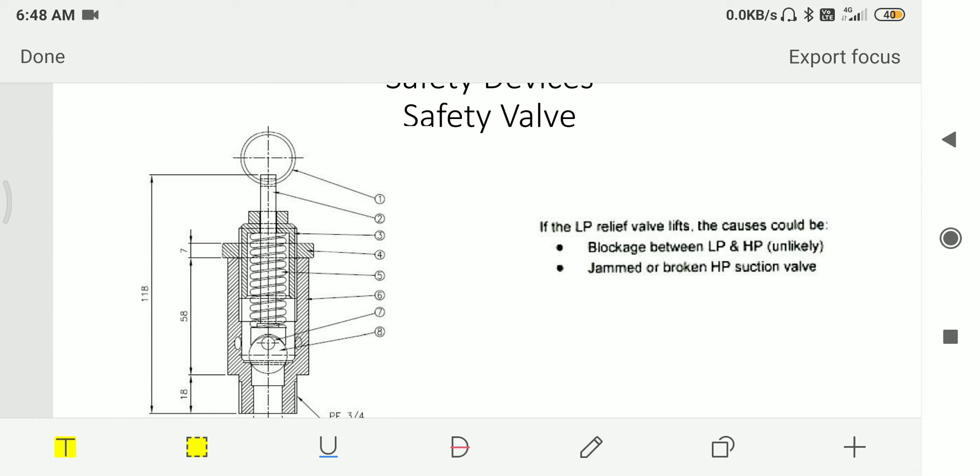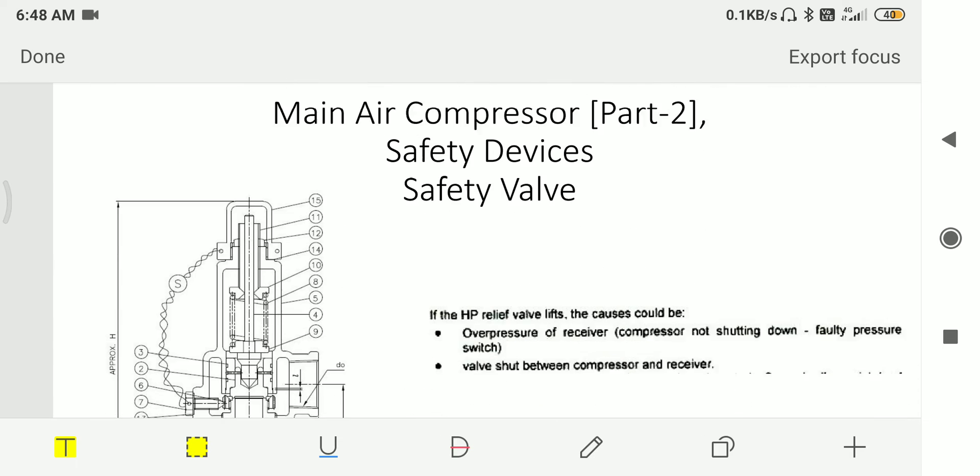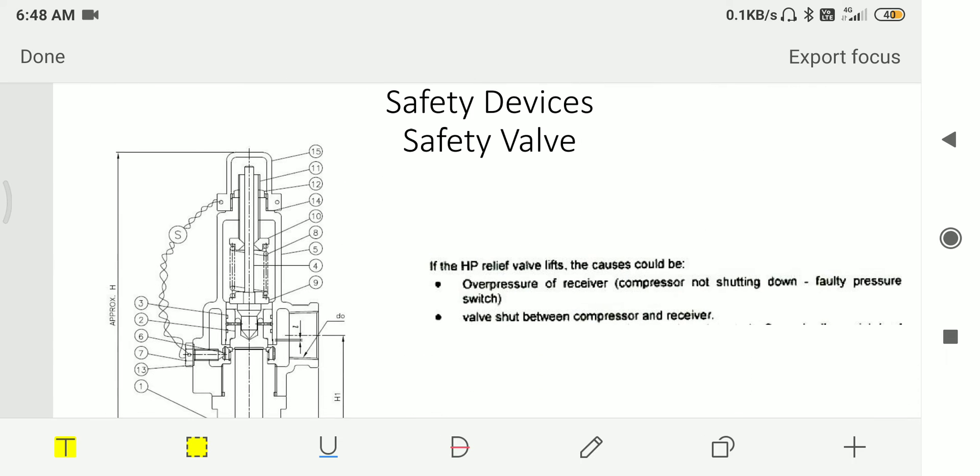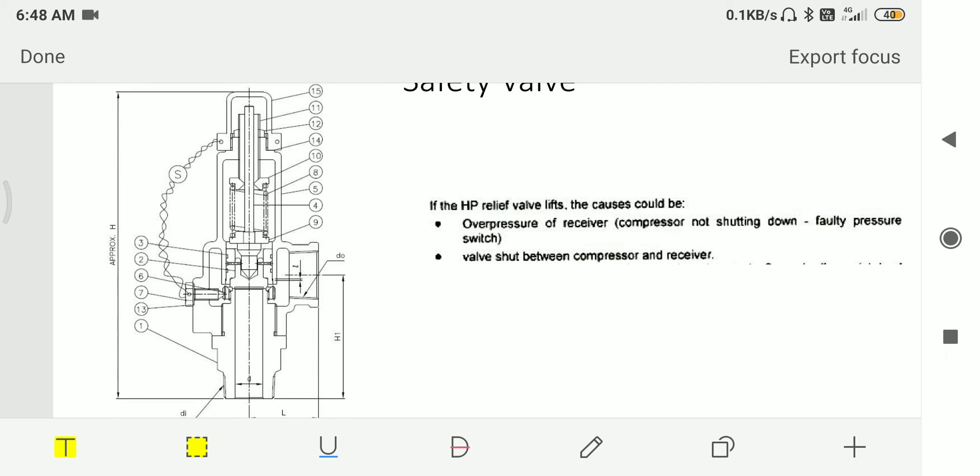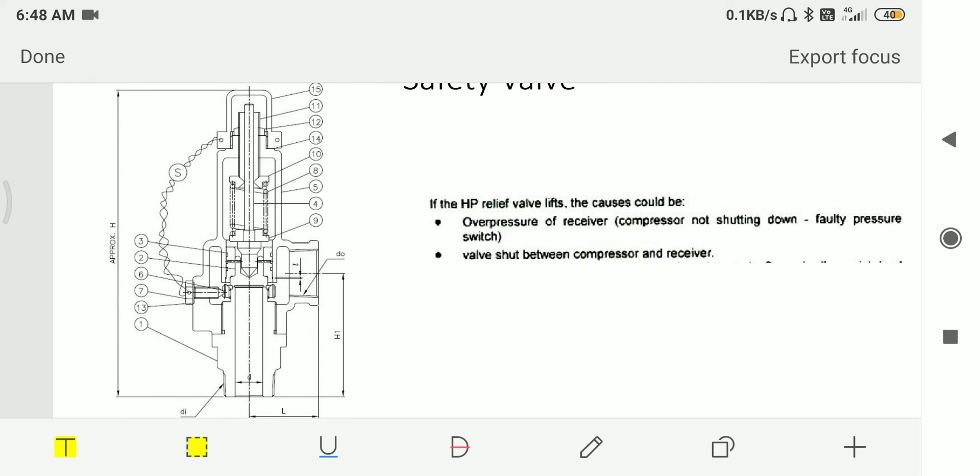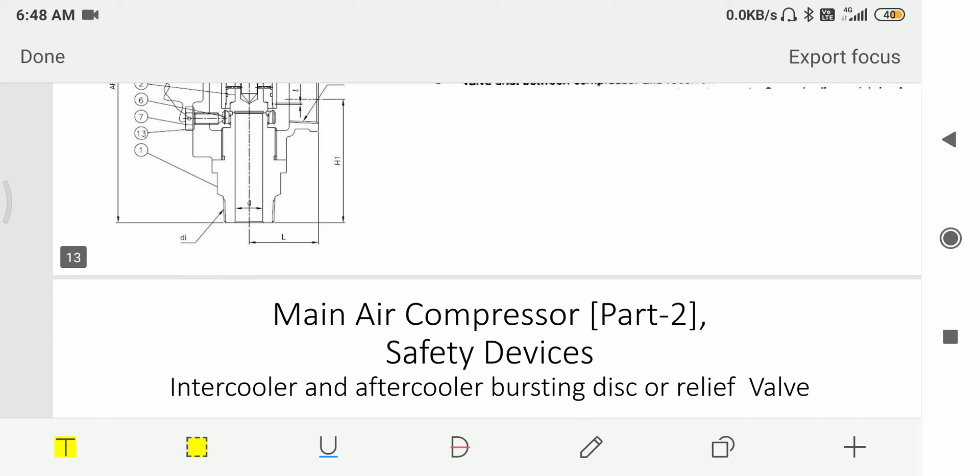If a low pressure relief valve lifts, the cause could be blockage between low pressure and high pressure, or jammed or broken high pressure suction valve. If high pressure relief lifts, the cause could be overpressure of receiver or valve shut between the compressor and the receiver.